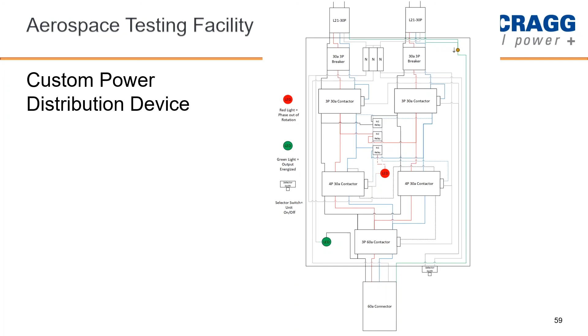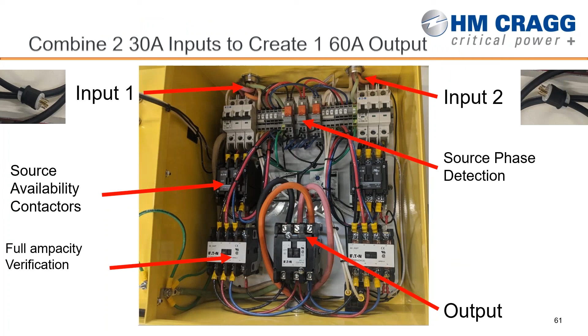We have on the next slide here, it'll show a 2 input device where we have a selection of input protection as well as some safety devices built into here for out of phase detection, an ampacity sensor to make sure we're not drawing 60 amps off of one side, as well as some indication lights to make sure that the customer is aware of how this device is operating, if there's an issue, what that issue might be, as well as a selector switch for the main input output. So we did all this design work up front, got it approved by the end user, and then we went to manufacturing for these small little, almost a junction box type product. So you can see in here, pretty wiring heavy solution, very custom.